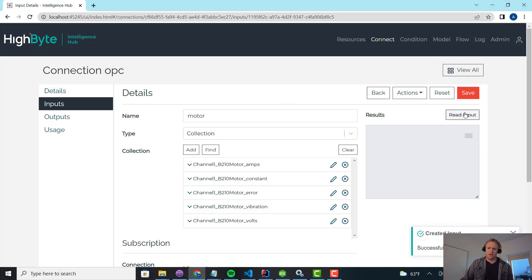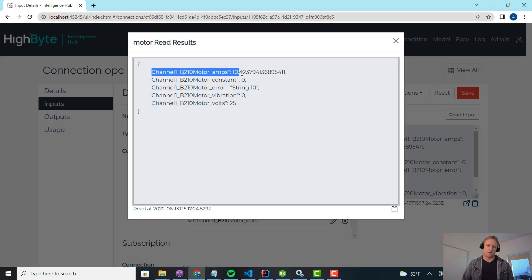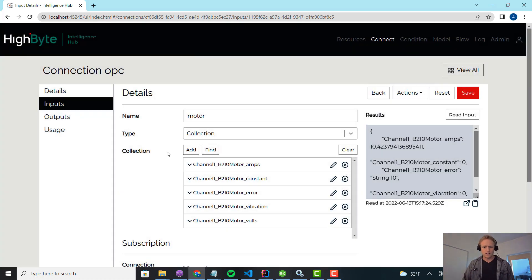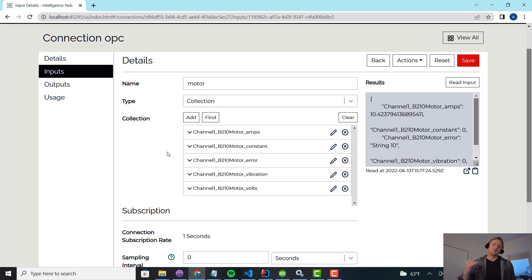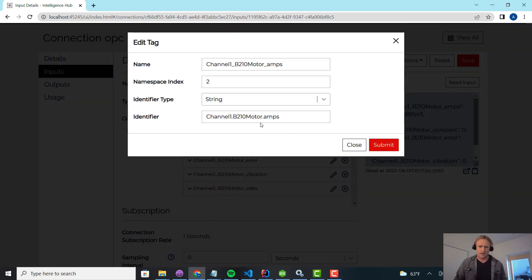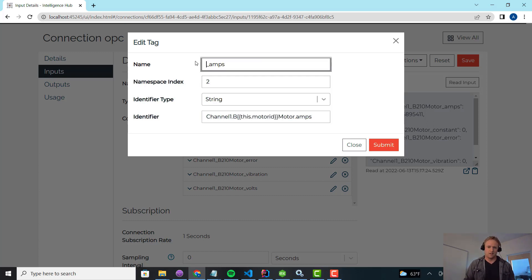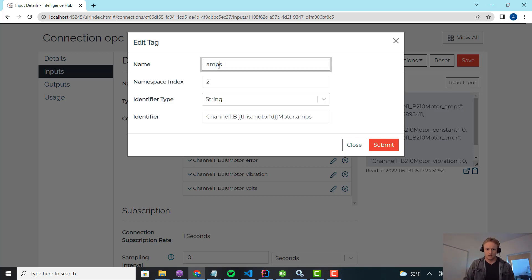If I do a test read, you'll see what HighByte is doing behind the scenes — reading each individual tag and returning it as a named value pair. In this case, this is motor 210 and string 10. It's the identifier. Now I have a collection of tags. What I want is to genericize this collection so it can represent all of those tags. I'm going to make an edit and replace the motor identifier with a template parameter — that's the syntax for that. I'll also remove the 210 from the tag name so I don't have 210 showing up in the actual name when indexing 211, 212, etc.